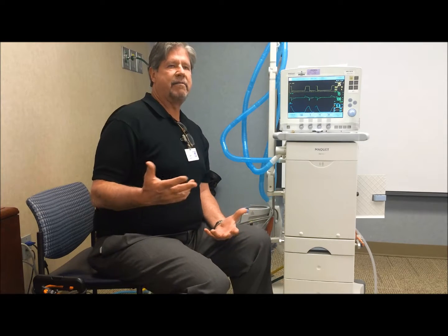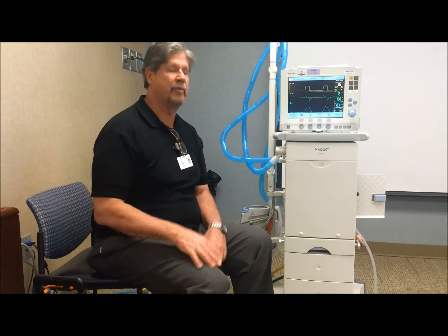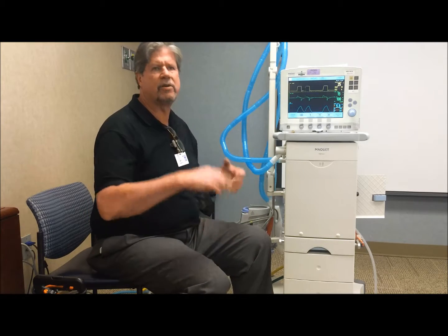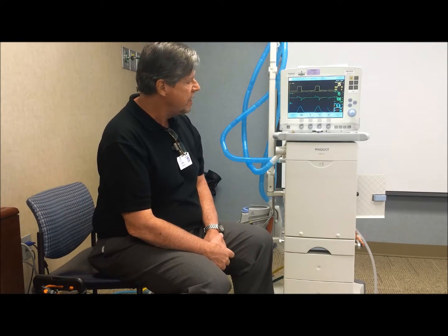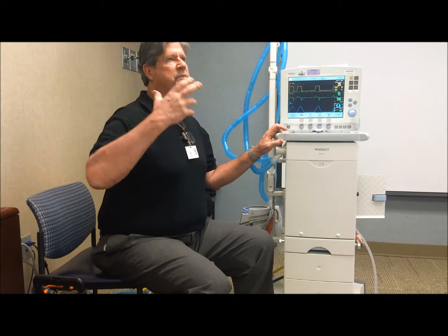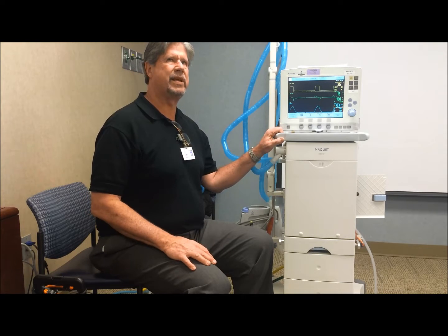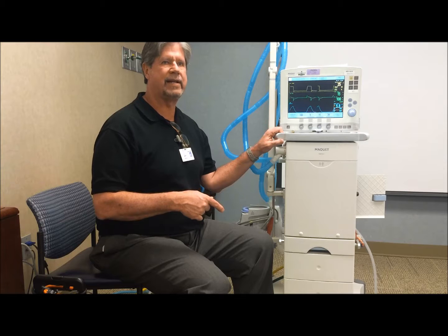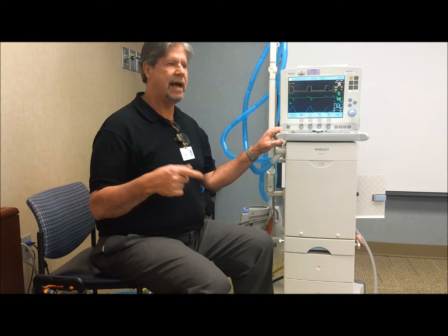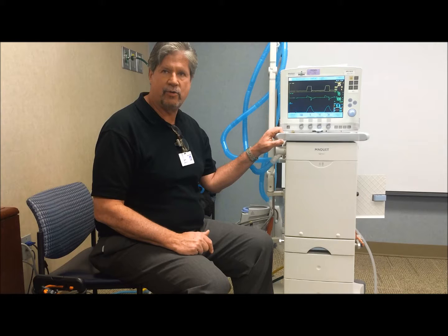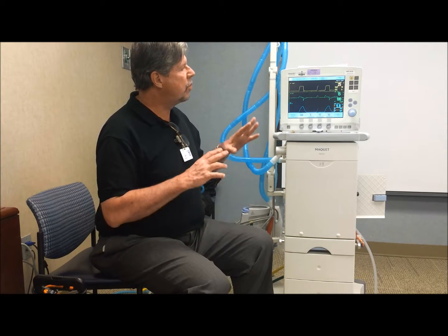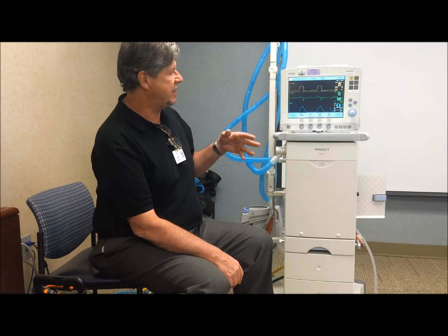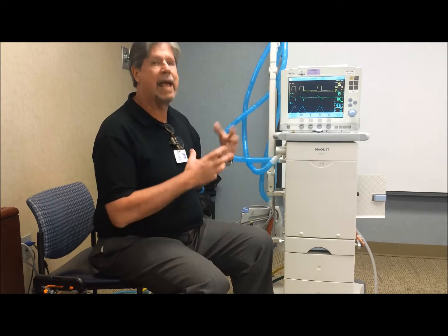So because of all that, hospitals said, oh God, do we really have to use helium? It's such a pain, I gotta go to the tank room, and plus we gotta find the right adapters and so on and so forth, and plus it's confusing. Because people were still thinking, well, how can we get a 70-30 blend if we're using an 80-20 tank? How can we get a 60-40 blend if we're using an 80-20 tank? Well, the ventilator will take care of that for you, right? So what Maquet did, they said, all right, well, let's make a ventilator that has the capability of doing helium.